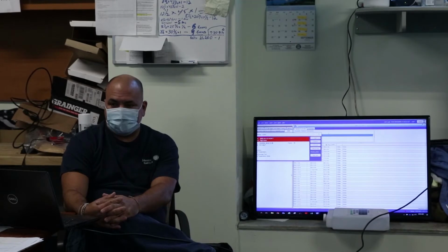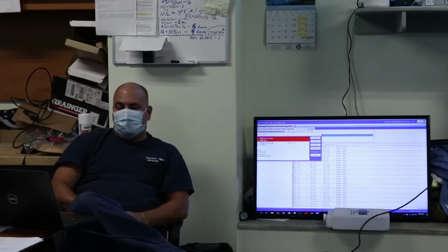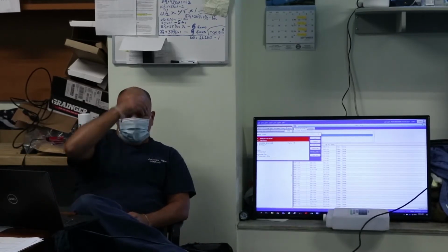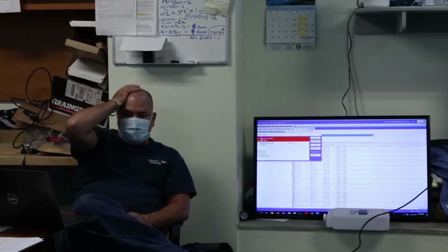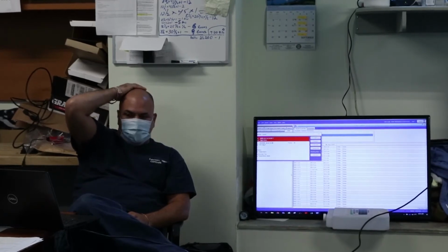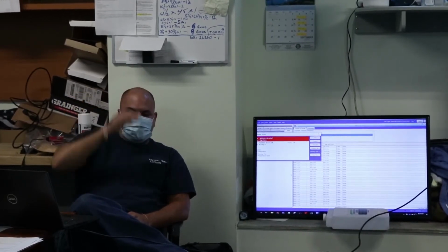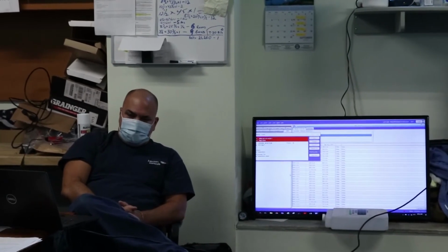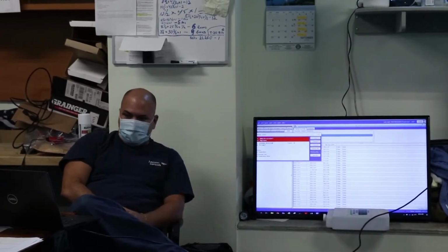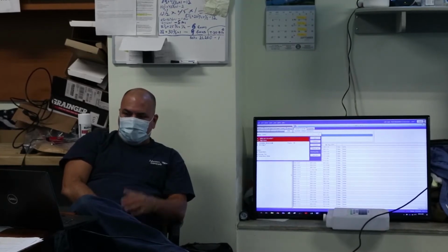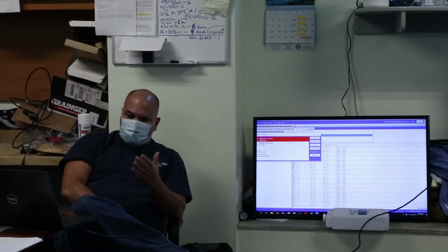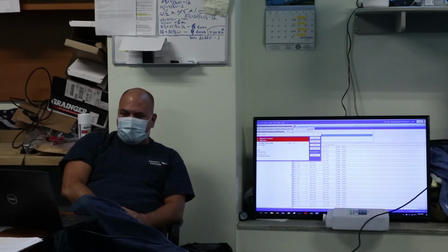So all I'm saying is how important it is to actually hit acknowledge on these alarms. I think that's why we had the fuel oil commissioning issues. I think that was the reason too, that the alarms never got acknowledged, like we talked about yesterday. So that's why you didn't get an additional pop-up on it. It turned red on the screen, but you didn't get the pop-up, right? Correct. Yes, you need to acknowledge the alarms, especially the critical alarms, to get them to continue to pop up.